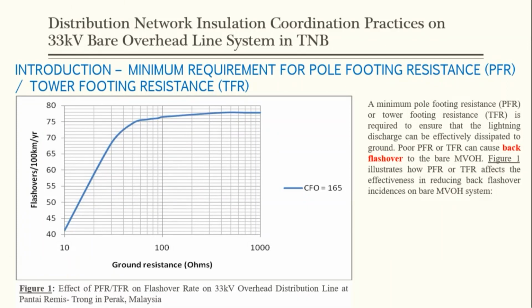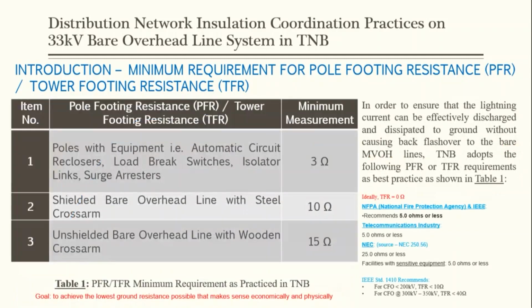Figure 1 illustrates how PFR or TFR affects the effectiveness in reducing back flashover incidences on bare medium voltage overhead lines. So, as you can see from the graph, the lower the ground resistance, the fewer the flashovers per 100 kilometer per year. So that is why we need to keep the ground resistance as low as possible.